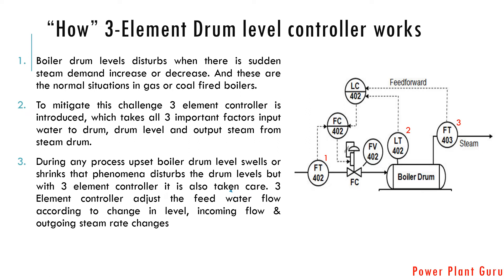Steam drum level is disturbed when there is any upset in the process — for example, a sudden increase in steam demand. This is when three-element level control is very important. If there is a sudden increase in steam demand, boiler drum pressure will drop. Dropping drum pressure leads to a phenomenon called swelling of the steam drum level. Swelling and shrinking are two important phenomena.